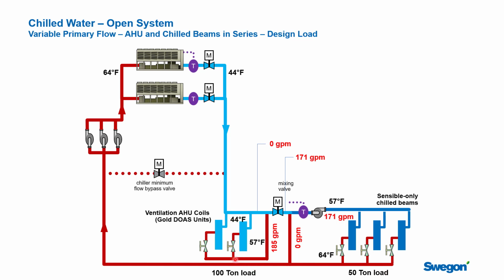Now, we saw before that if this is a 100-ton load at the air handling units, we would heat water from 44 to 57, and we would create 185 GPM of 57 degree water. That makes sense. But this load has dropped off significantly for some reason. And now what happens is you only need 171 GPM of 57 degree water to meet the 50 tons of load. So we'll heat that water from 57 to 64. It'll be 171 GPM. That seems fine from a temperature point of view. Have a look at what it's doing to your flow rates.